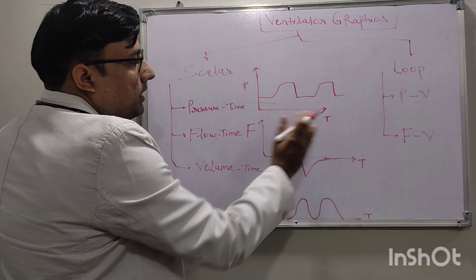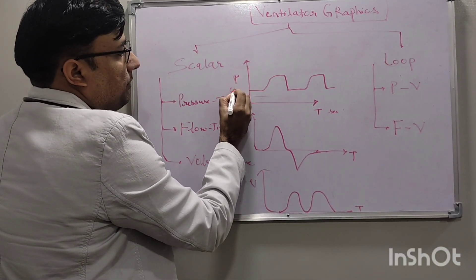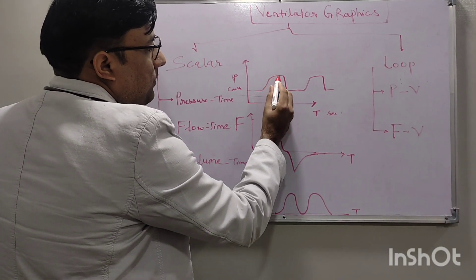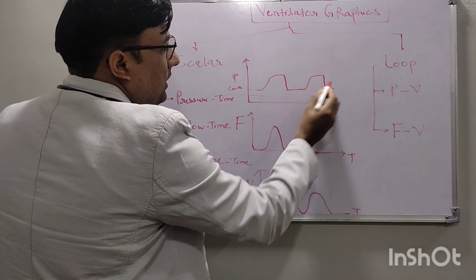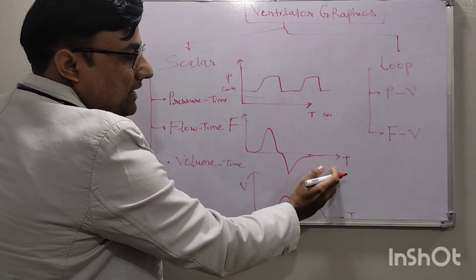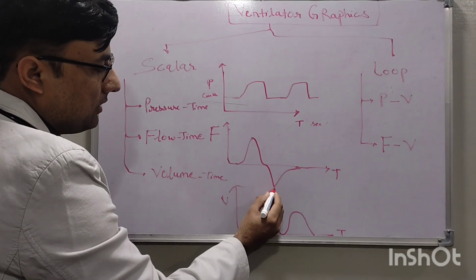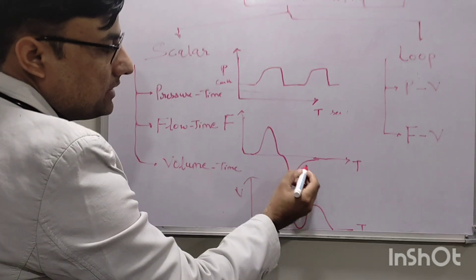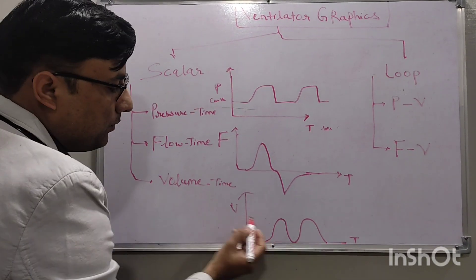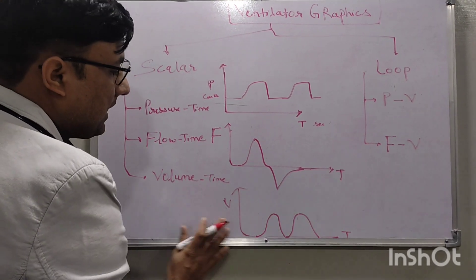In the pressure-time curve, on the x-axis will be the time in seconds and the y-axis will be pressure in centimeters of H₂O, showing PEEP and PIP. In the flow-time curve, the x-axis is time and y-axis is flow — inspiratory flow during inspiration, then expiratory flow. In the volume-time curve, the x-axis is time, y-axis is volume, and this represents the tidal volume.